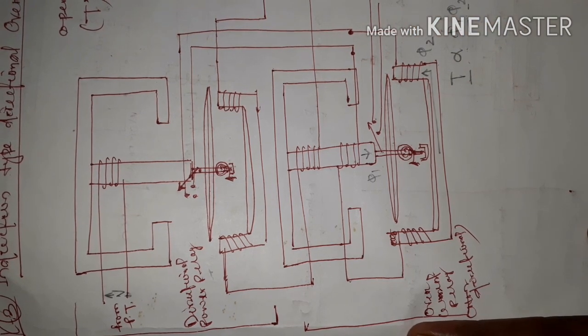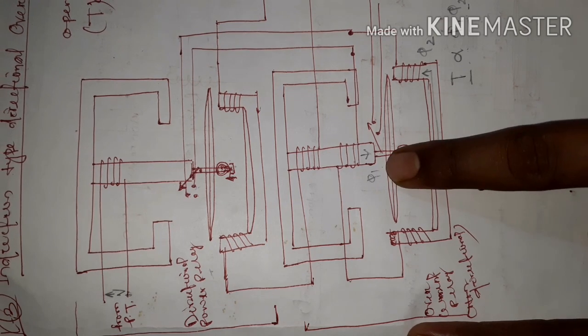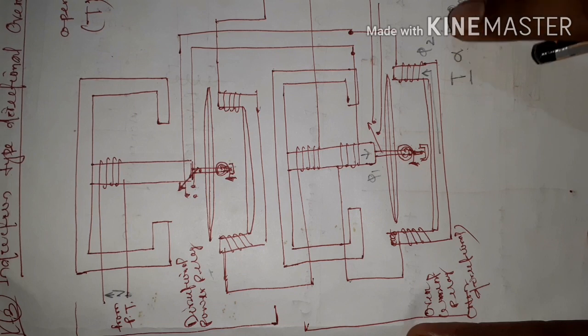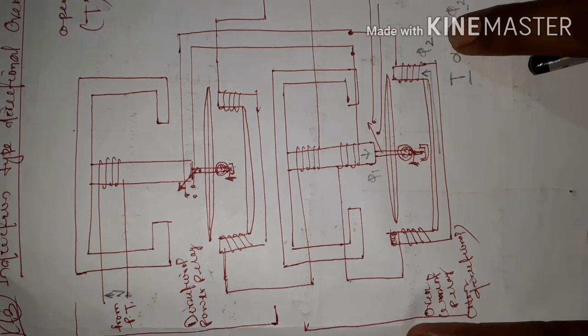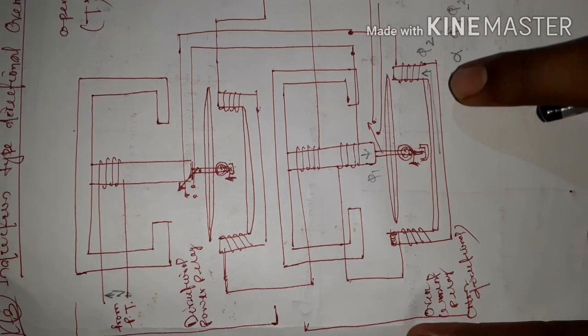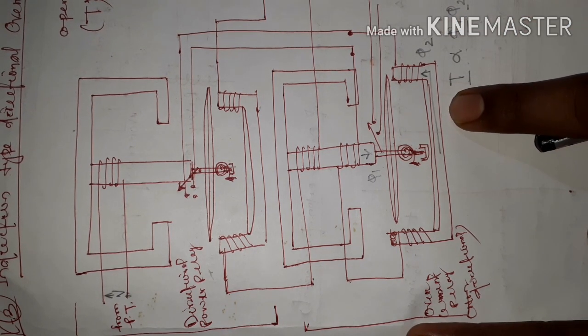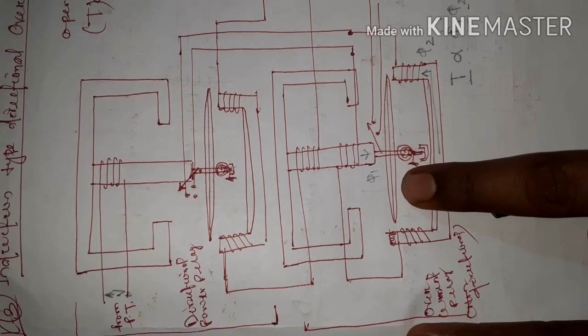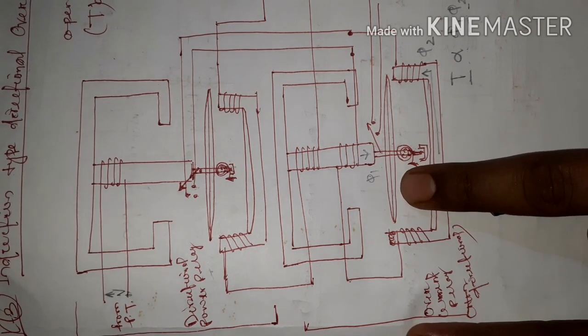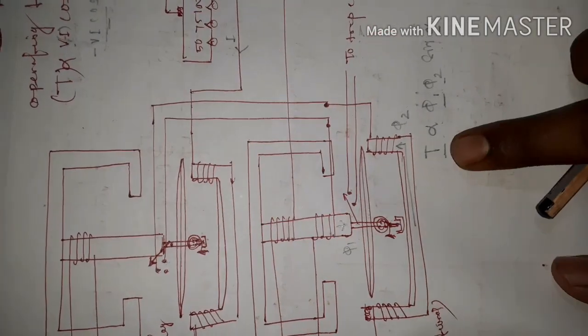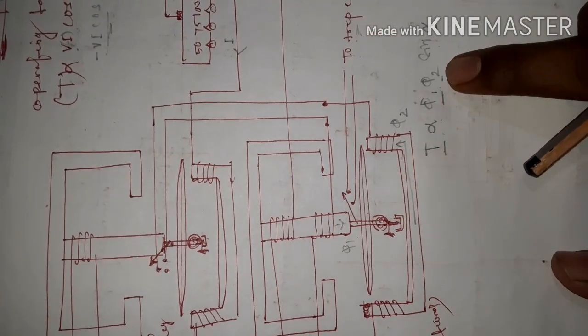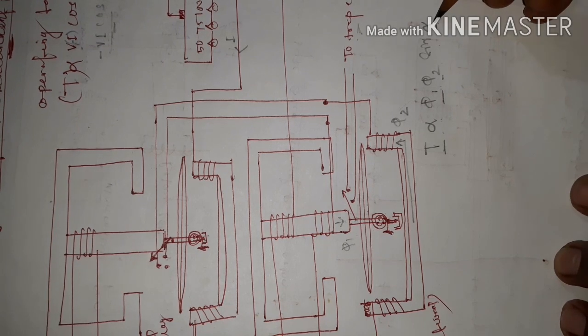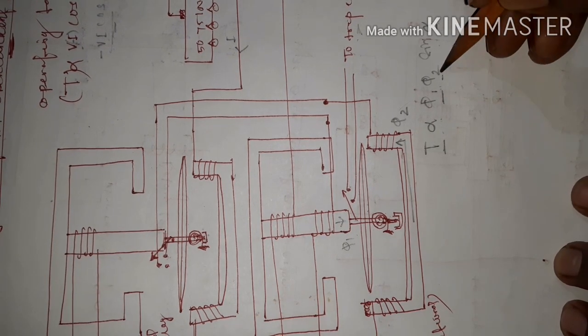When the directional power relay sends a signal to the overcurrent relay, two fluxes are developed. Flux φ1 is developed by the upper electromagnet, whereas flux φ2 is developed by the lower electromagnet. An operating torque is then developed on the aluminum disc, represented as T proportional to φ1·φ2·sin α, where α is the phase angle between φ1 and φ2.